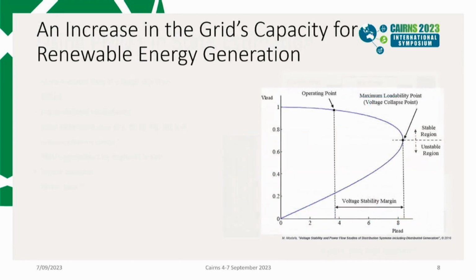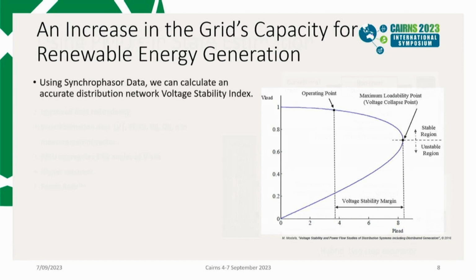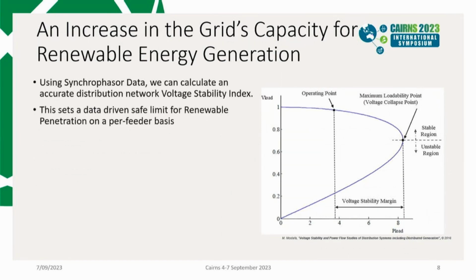Another outcome was an increase in the grid's capacity for renewable energy generation. Today we use conservative limits to stay within the voltage stability index, but not all feeders that are connected to the distribution grid are operating anywhere near their maximum loadability point. And so in general, using the synchrophasor data that we gathered, we can calculate an accurate distribution network voltage stability index on a feeder by feeder basis. And so this sets a data-driven safe limit for renewable penetration on a per feeder basis.